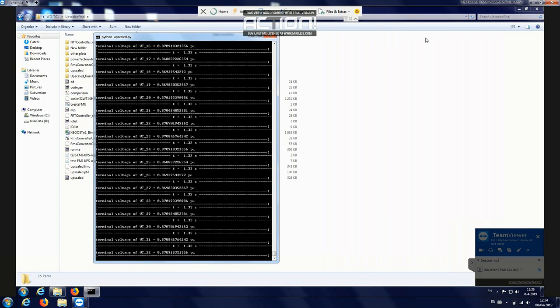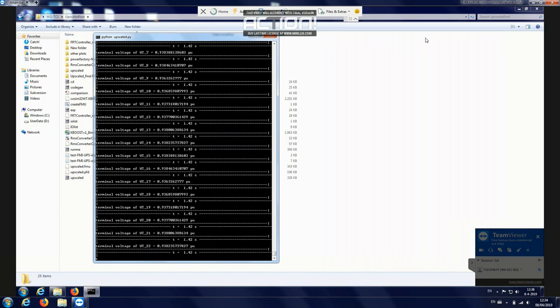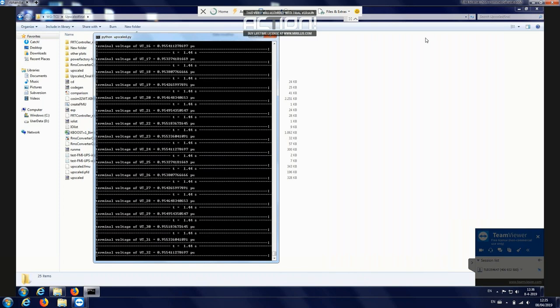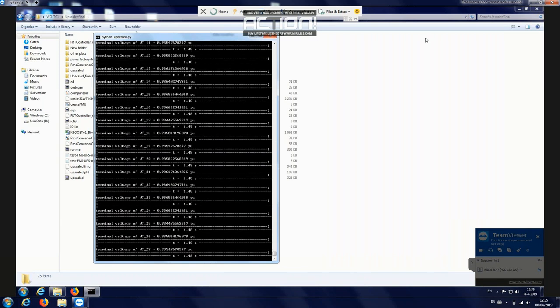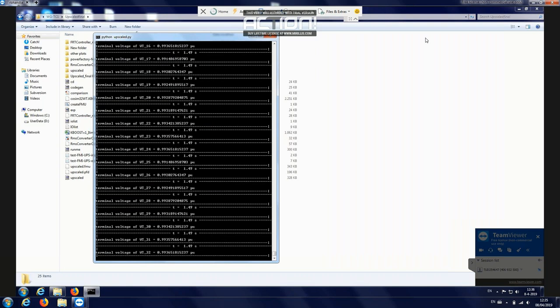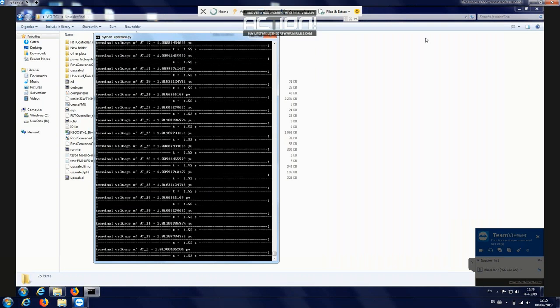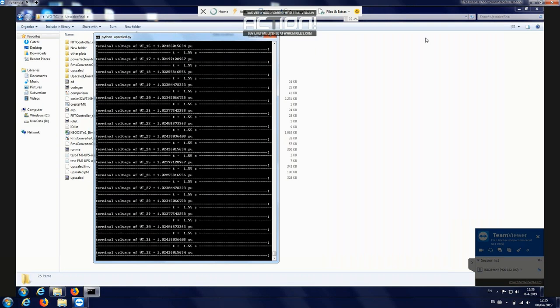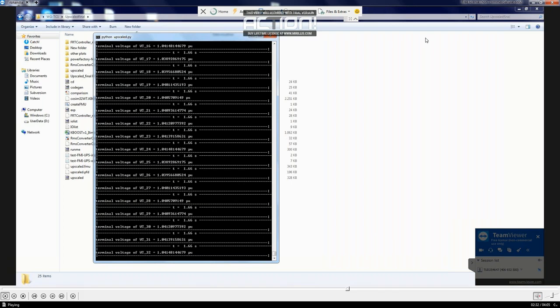As you see now, as time increases, the voltage has been ramped up to 0.9 PU, which means our controllers are working fine and providing the FRT support that is needed. Now we are almost back to the levels we started with, which is 1.04 PU. I will move a bit forward.